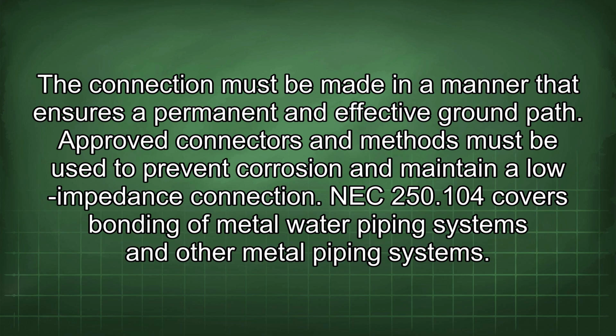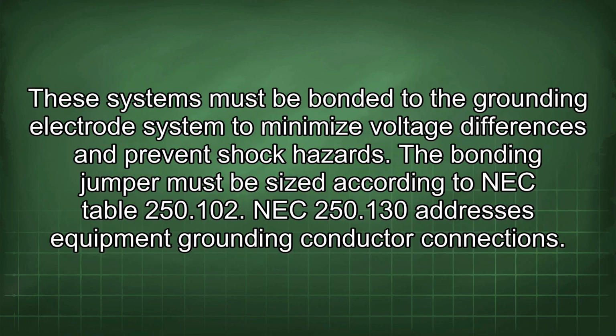NEC 250.104 covers bonding of metal water piping systems and other metal piping systems. These systems must be bonded to the grounding electrode system to minimize voltage differences and prevent shock hazards. The bonding jumper must be sized according to NEC Table 250.102.